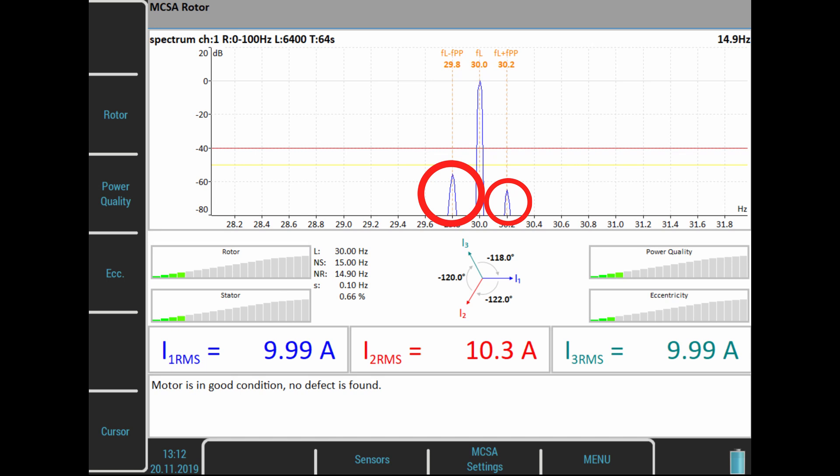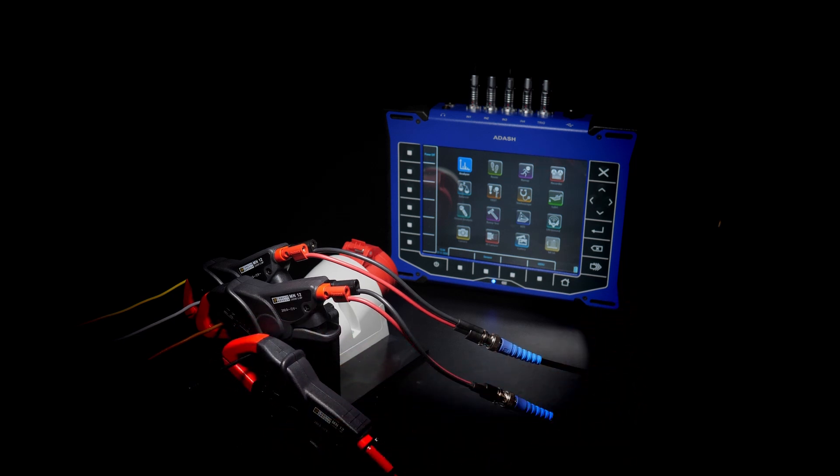Individual defects can be distinguished from each other according to the amplitude bands and the frequency or other signatures. The basis of this method is to measure the course of the stator current of one or more phases in the time domain and its subsequent spectral analysis.